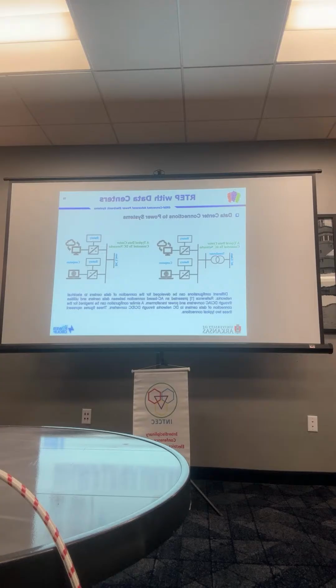On the right side, we have typical data centers connected to DC networks. This is a new configuration. Based on this, we no longer use transformers; we are able to connect data centers directly to the DC network. If we have a DC line in our power system, we can connect the data centers directly to those DC lines through DC-DC converters. It is said that this topology is more efficient and can bring new advantages for power system operators.